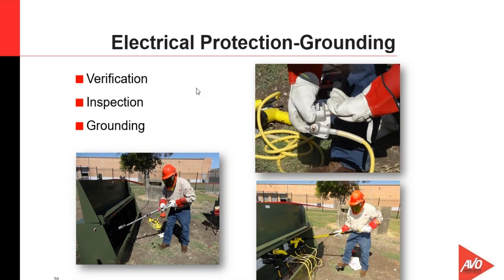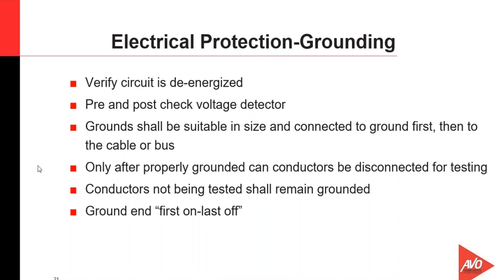And then in the installation process, using a hot stick, we would install the grounds. They go on the ground first and then to the phases last. We would take them off in reverse order. But in the ground installation, all of the PPE requirements have to be met in order to adequately install the ground safely at the site that we're going to be testing.